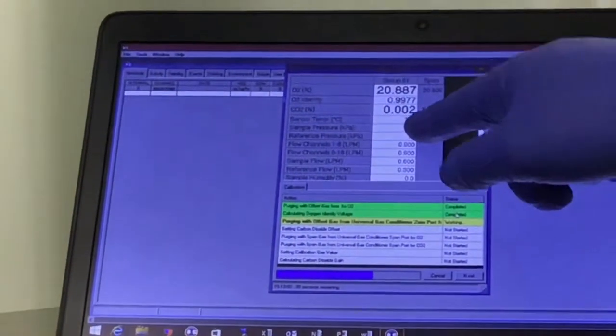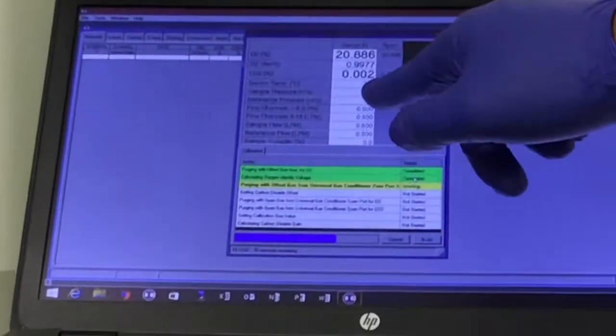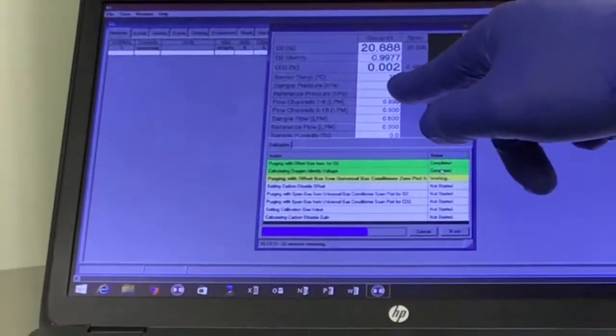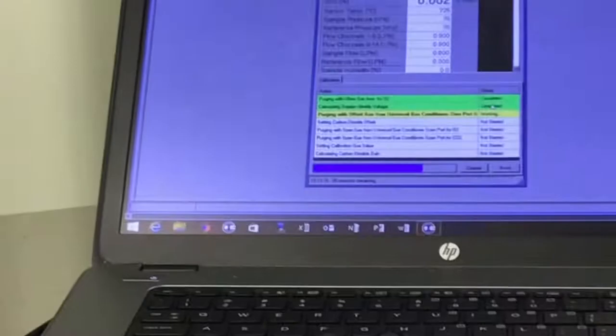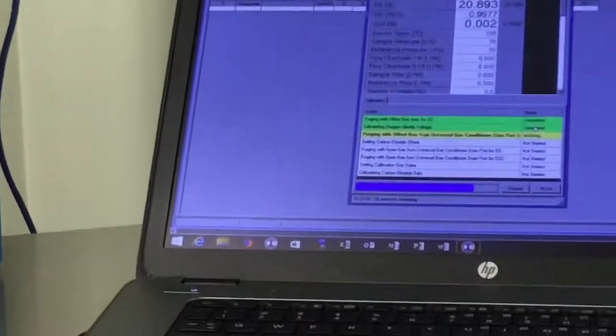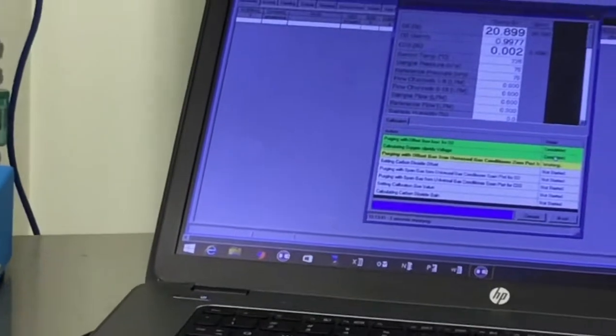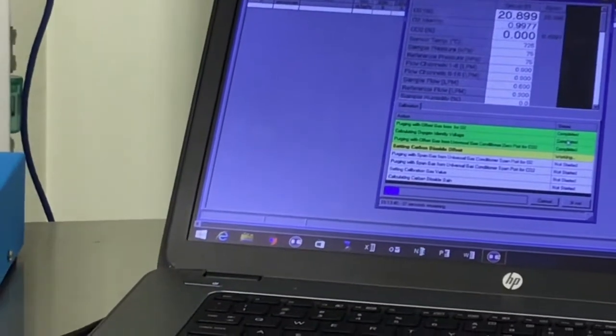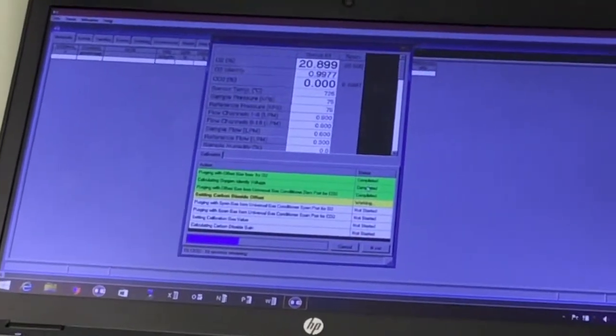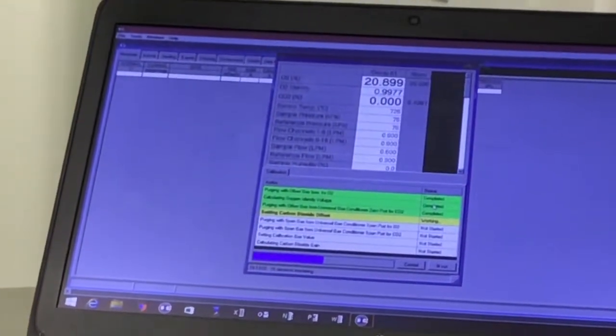Here, I was telling you guys, never open that O2 sensor to try to see what's in it, because what's in it is very hot, 725 degrees Celsius. Actually, the way the O2 sensor works is two tubes. They put a reference air in one tube, they put the actual gas in another tube, and they heat both to 725. Guess what happened? It tried to keep itself at equilibrium. So now some O2 molecules will migrate from the side that has the most to the other side. Since we know this is the known gas, based on how many migrated, we know the actual concentration of the other. It's pretty cool, but it's not cool to touch it. It's hot.